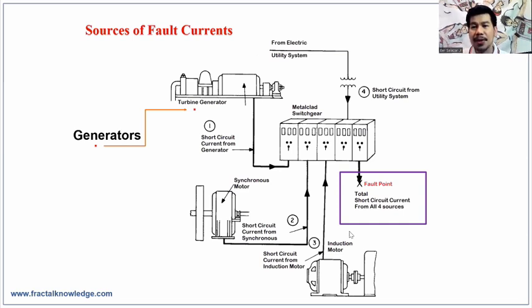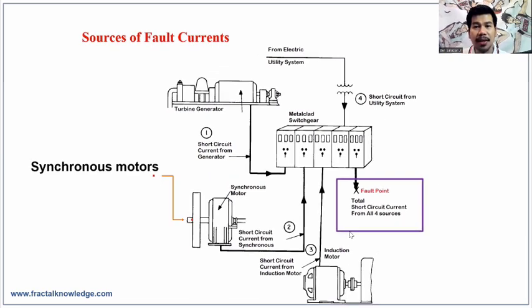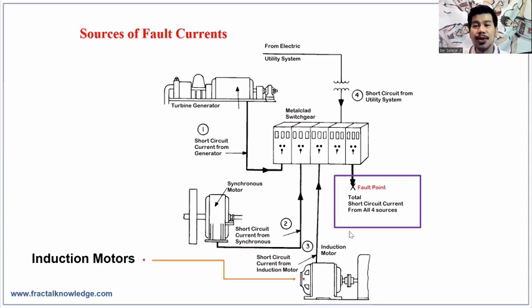The third source is synchronous motor. This motor acts as a generator at an instant of a fault, thereby contributing fault current caused by the inertia of the load that drives the rotor. A DC current is present in the winding of a synchronous motor, so in the event of fault, the synchronous motor becomes a generator.